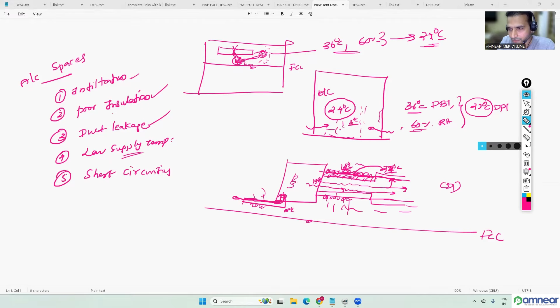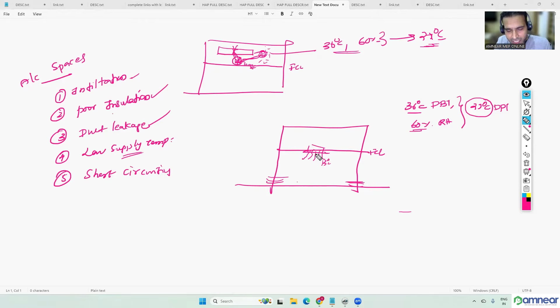Now low supply temperature can also be an issue. For example, if you have a false ceiling and this is a diffuser, the temperature of air coming out from the AC equipment is normally 13 or 14 degrees Celsius. Accordingly, we have designed it. But in hot and humid times, if the infiltration is high, even at 13 or 14 degrees Celsius condensation can come, but infiltration we have to neglect. Low supply temperature is also a reason for condensation, because instead of 13, sometimes the supply temperature is 10 or 9 degrees Celsius. When the surrounding air, with a dew point temperature much higher than the supply temperature, has contact with this air, condensation can come. Even in a perfectly sealed building with very limited infiltration, a low supply temperature through the diffuser or from the machine can result in condensation issues.